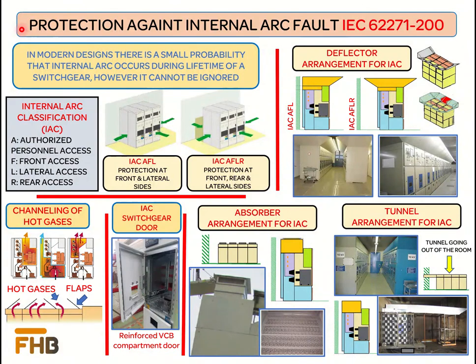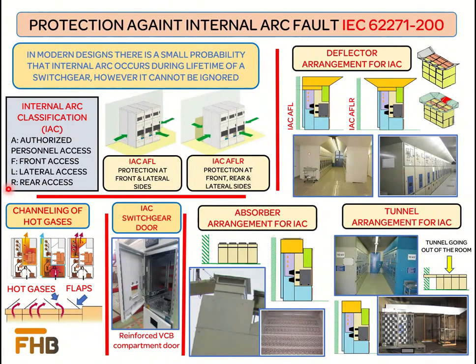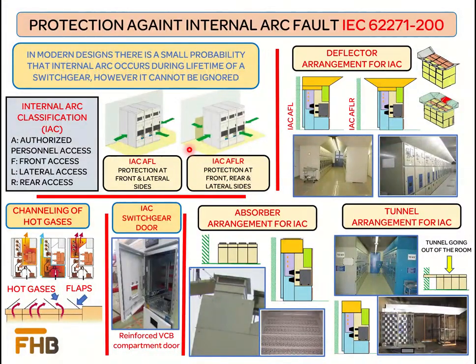IEC 62271-200 defines the accessibility class for internal arc classified switchgears. Accessibility Class A is restricted to authorized persons only, while Class B is for unrestricted areas including the general public. The letters F, L, and R represent the sides of the switchgear where protection is provided in case of an internal arc fault: F represents the front side, R represents the rear side, and L represents the lateral sides. If the switchgear installation is against the wall, normally AFL classification is considered. AFL-R classification provides protection on all sides of the switchgear. As per IEC 62271-200, the recommended test durations are 1 second, 0.5 second, and 0.1 second.